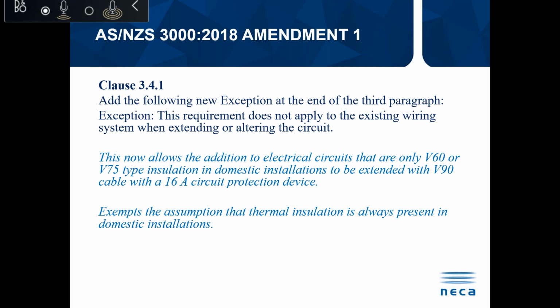It exempts the assumption that thermal insulation is always present in domestic installations. If this wasn't the case, you would only be able to put a 12 amp circuit breaker on any additional add-ons to existing circuits.